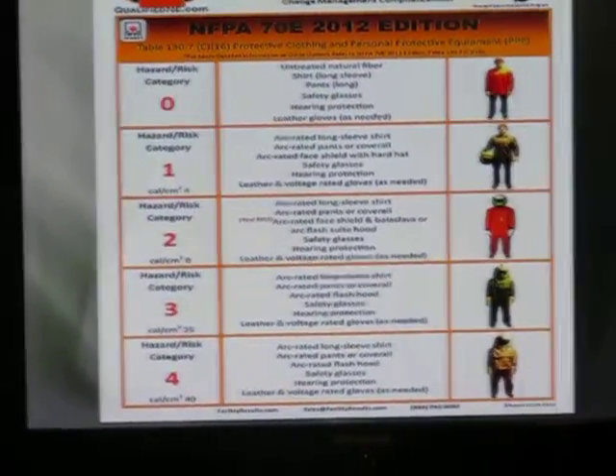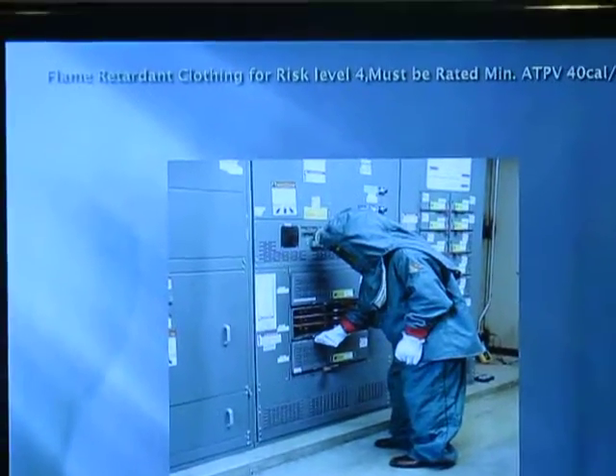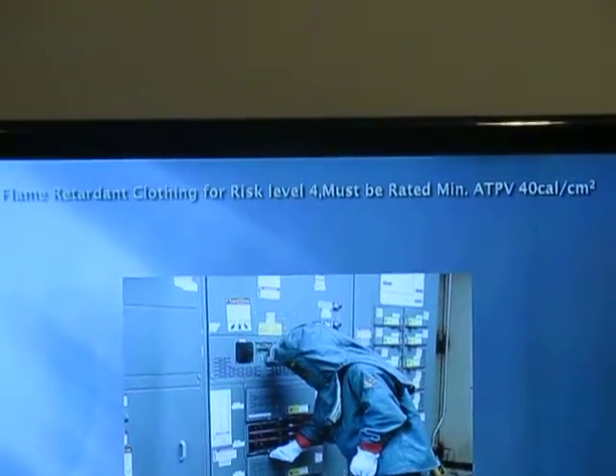In category 1, it gets thicker. You have to add more layers until you get all the way to 4, which, if you've ever worn that, is very uncomfortable and very, very hot. Flame retardant clothing, this is a level 4. Does anybody see a problem with this picture? Not wearing the protective boots, proper PPE. Slippers on or something. Yeah, those are not electrically rated boots or shoes.